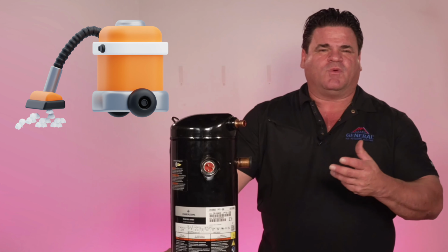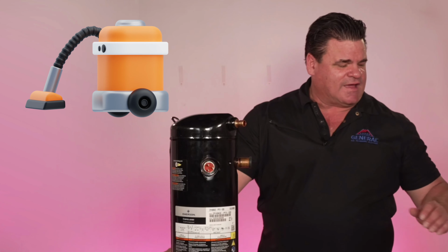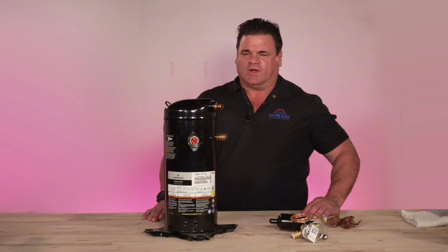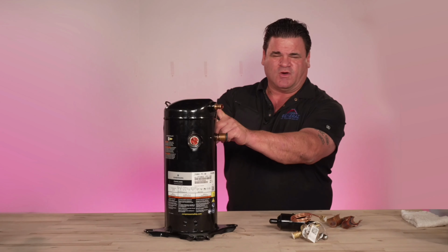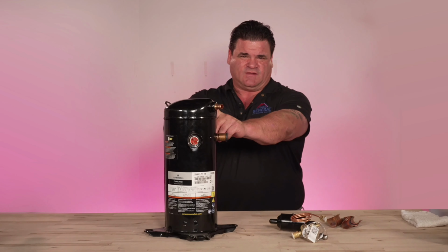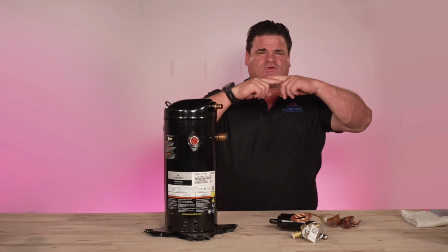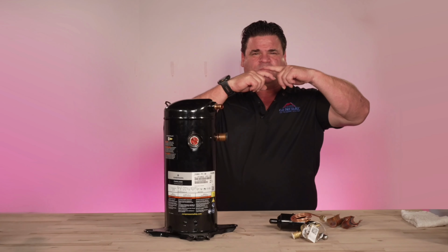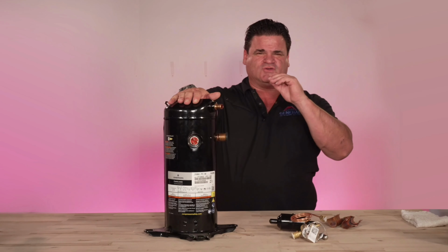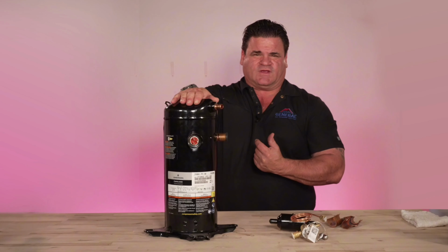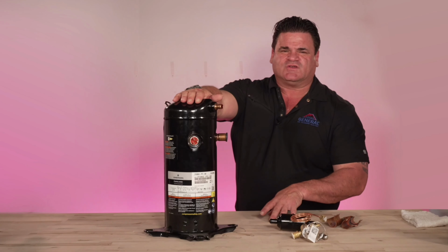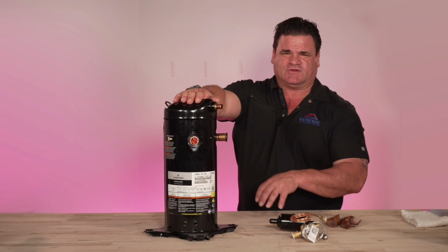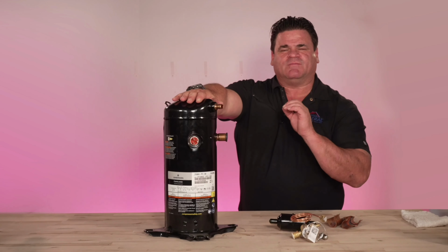And pulling a vacuum pulls all the non-condensables and everything like that out of the system. Very important step. So inside this compressor, inside this motor, there's an internal overload safety. An internal overload safety is typically two dissimilar metals that when they heat, they bend apart and the system shuts off. There's no longer current able to flow through this. Now, if the technician doesn't know how to diagnose this properly, then they're going to misdiagnose your system as fail. It shouldn't happen. It does happen.